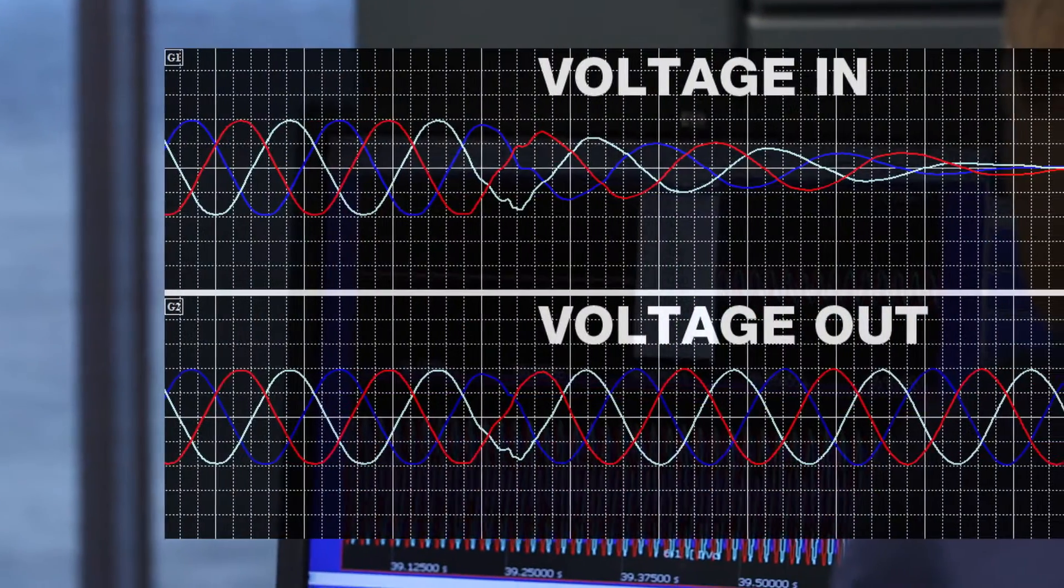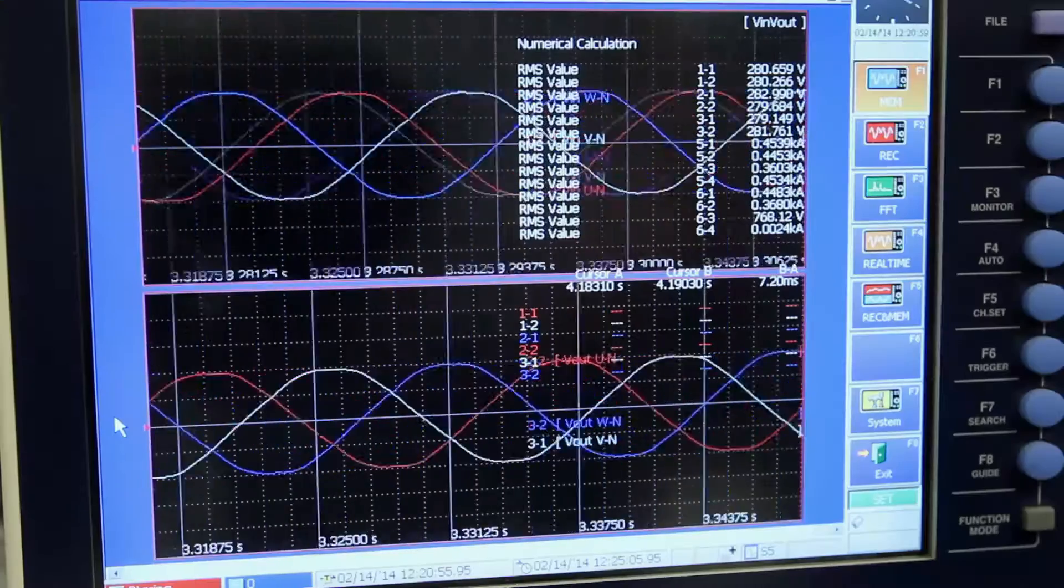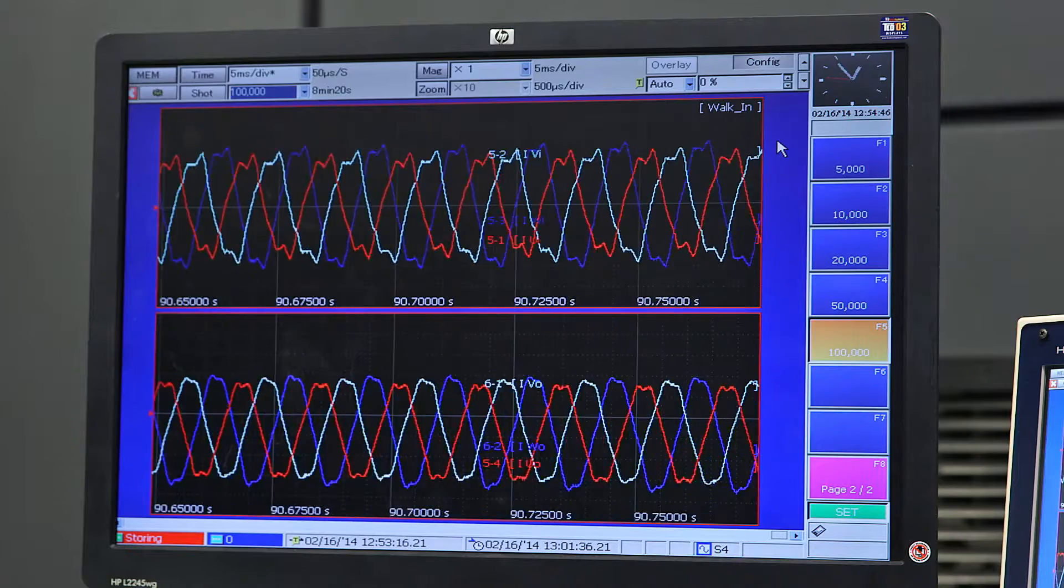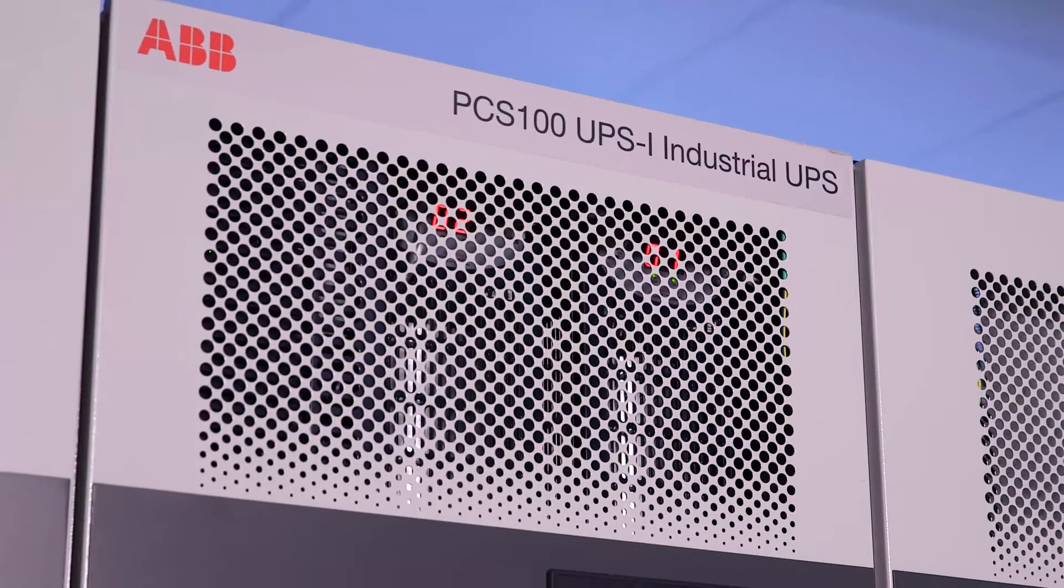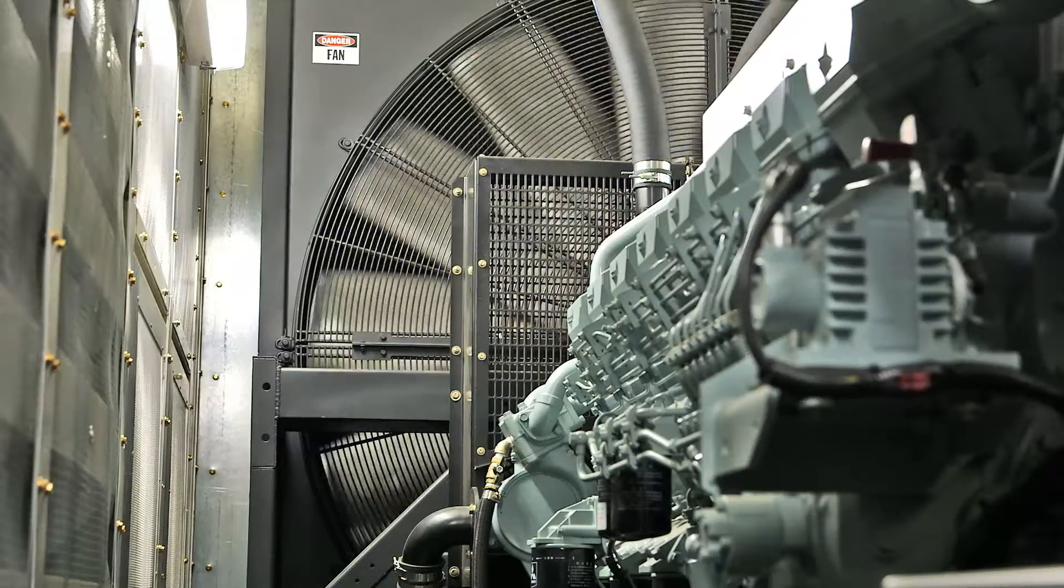Short-duration power quality events such as voltage dips and swells are taken care of by the UPS-I without need for the generator to start. If confronted with an extended event, ABB's PCS100 UPS-I bridges the time between the utility failing and the generator starting.